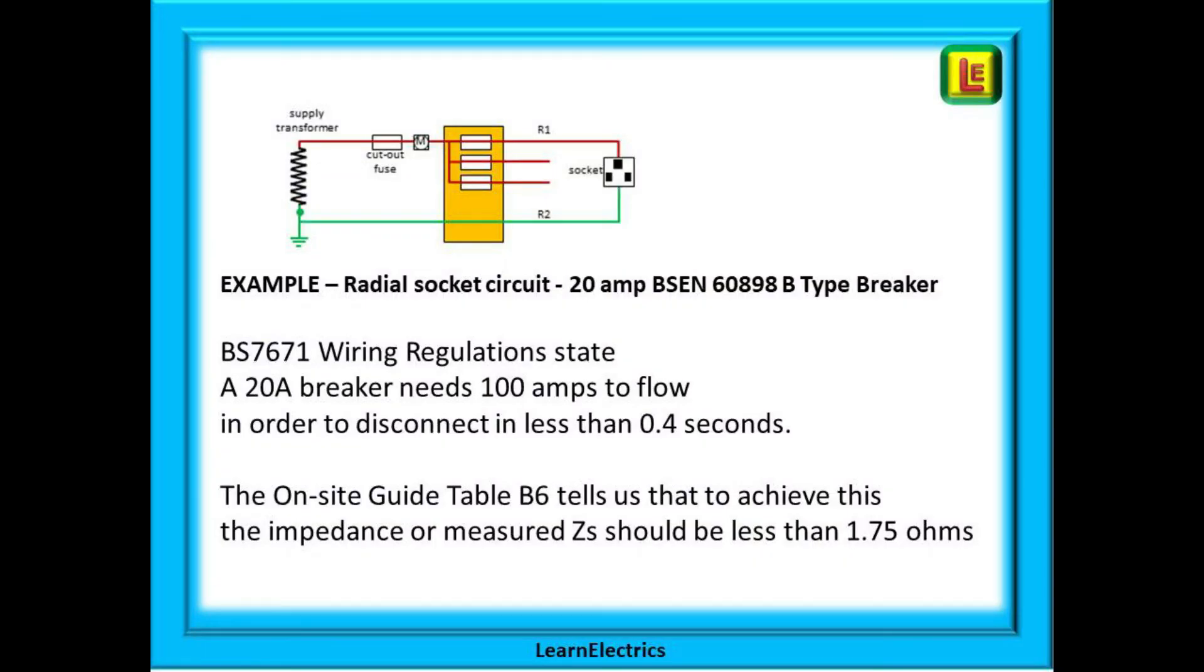In the UK our voltage is fixed at 230 volts AC and we use this value for all our calculations. Using our 20 amp radial socket circuit as an example, it is protected by a 20 amp B type MCB, and the wiring regulations tell us that this circuit would need to have at least 100 amps of fault current to flow in order to guarantee that the MCB will operate in 0.4 seconds or less.